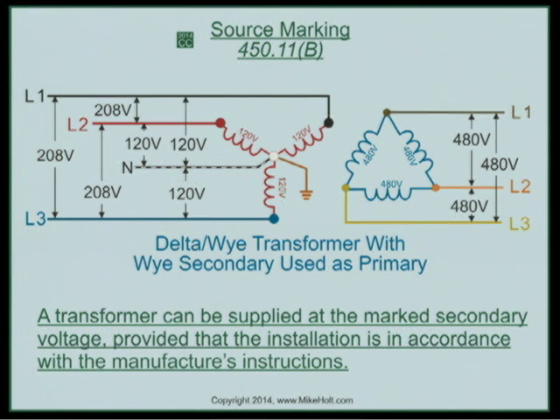What happens if it's all over the place? What happens to the primary? You're saying... I mean, I can see that for feeding a motor, you needed to run a motor with a specific, balanced load on the 480. But now you have parking lot lights that are very difficult to balance because they're on different phases. I'm not aware anywhere, whether it was a delta or a wye delta, that I have to balance my phases, that would have had anything significant.